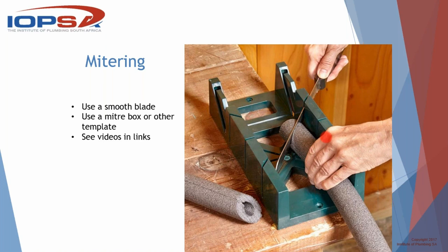What works even better than that is if you get those wide hacksaw blades. It's about 25 millimeter wide and it's got teeth both sides. Get that, because then it doesn't flex as much. And you take one side of that blade and you take the teeth off and you make it a sharp, like a normal penknife blade, turn it around, and that cuts through lagging beautifully. There's no burrs. It's a straight edge. It's beautiful to be able to join and glue.